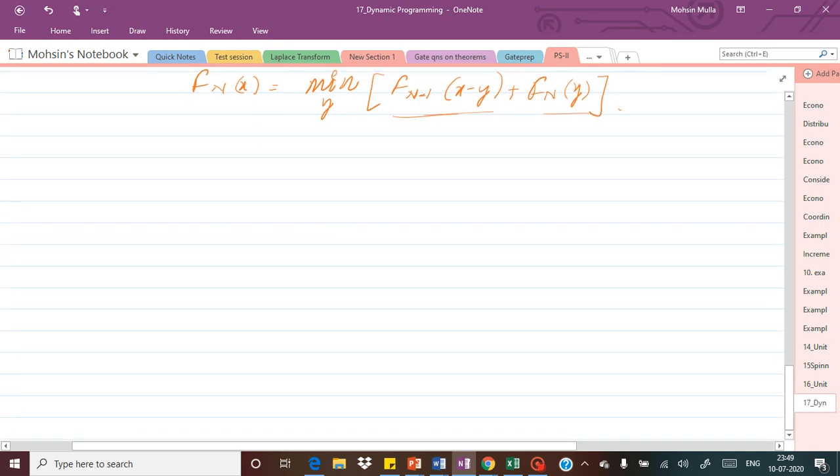From this particular recursive relation, it is easy to find out the combination of units which will result in minimum operating cost for loads varying in small steps from the minimum permissible load of the smallest unit to the sum of the maximum permissible capacities of all variable units. Therefore, with this procedure, the total minimum operating cost and the load shared by each unit of the optimal combination are automatically obtained for each load.